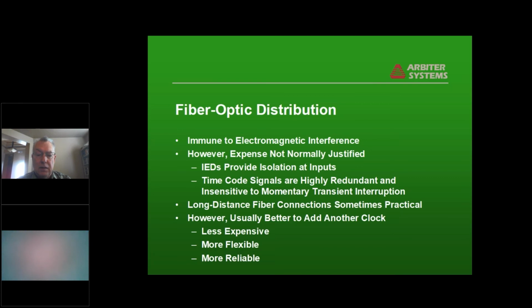And the reason that you generally don't need to use fiber optics is the IEDs already provide galvanic isolation at their input. And the time code signals are highly redundant. What that means is if a transient happens and it affects one of the bits on an IRIG signal, the IED will recognize that using that error bypass I talked about before. It won't follow it, it'll reject it because it looks for a consistent time change for 3 to 5 seconds before it'll accept it. So a momentary interruption of a signal doesn't really have much effect. That's one of the nice things about time code signals, they're highly redundant. We know that the time advances 1 second for each second. When something else than that happens, we're highly suspicious of it.